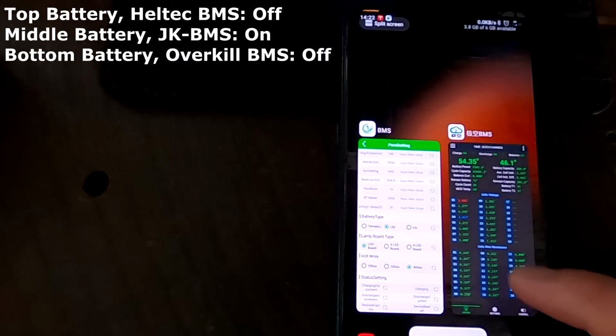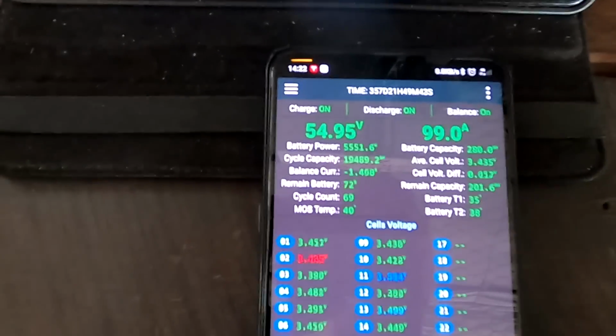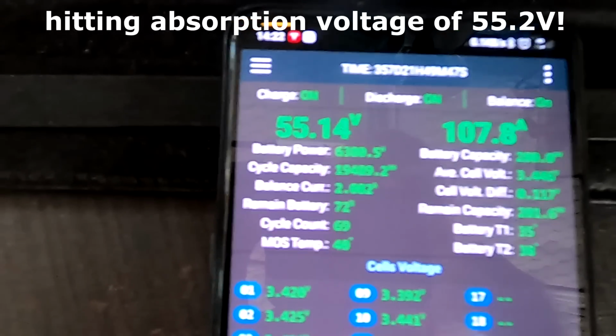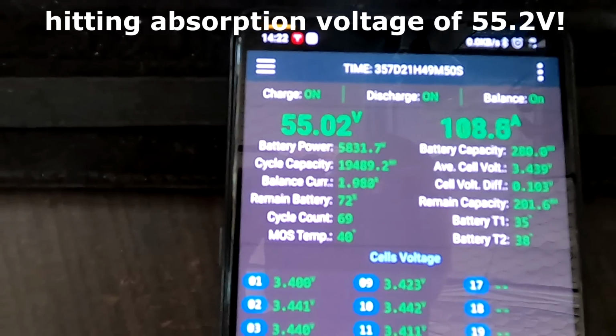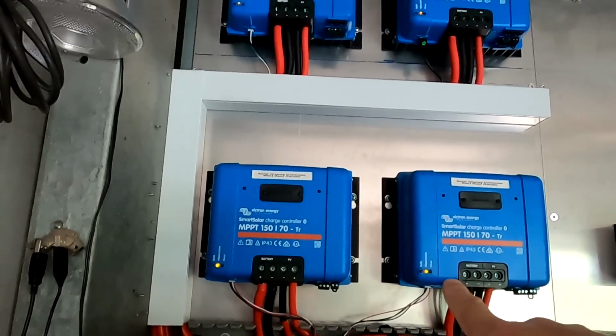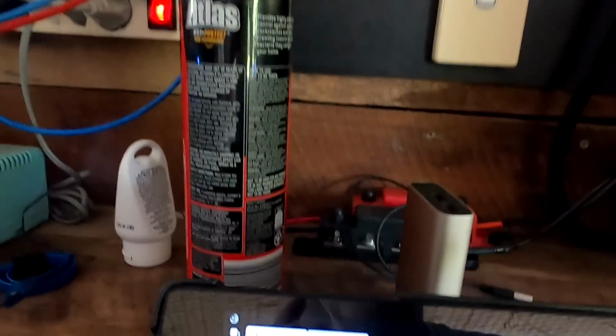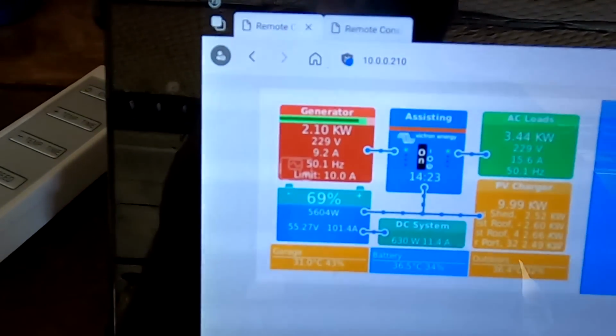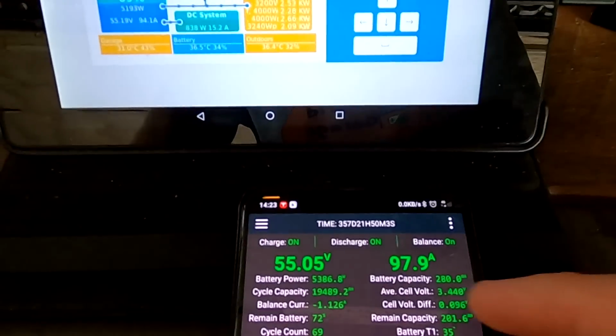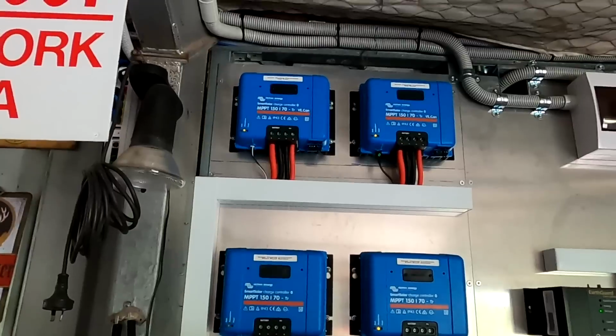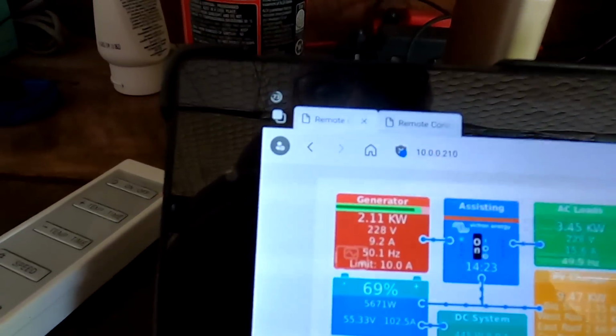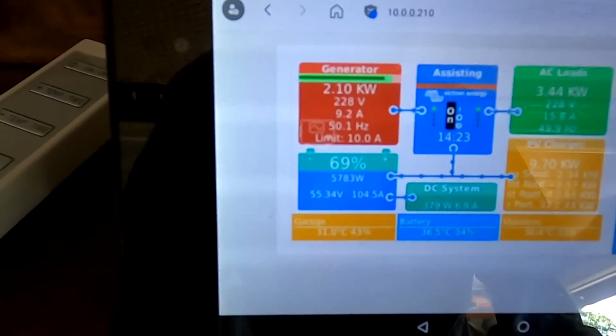Yes, successful. There we go, 100 amps. Yeah, that is too much. 117 is a bit too much for my taste. They need to look into this. And I just realized all the solar charge controllers have entered absorption stage now, even though we have only 70% state of charge, because of the voltage drop here across this one battery bank. They thought, well, it's time to go into absorption. We have reached the voltage. Look at this, 55.2 volts. Insane.